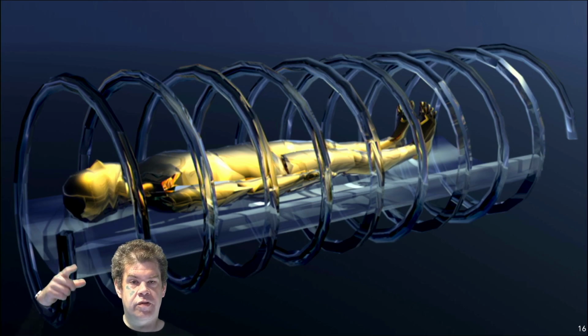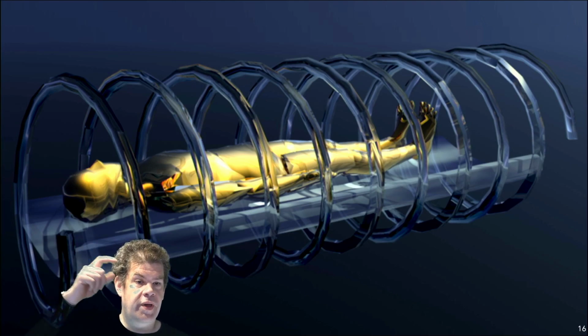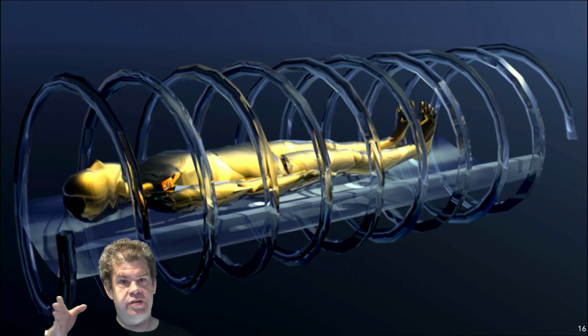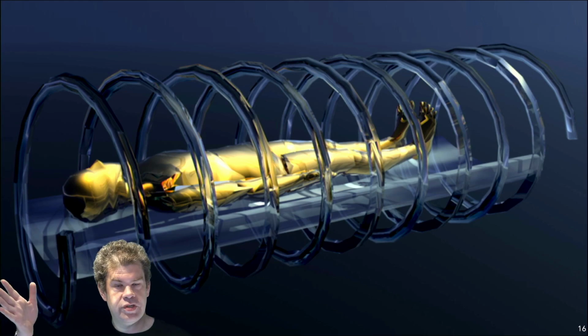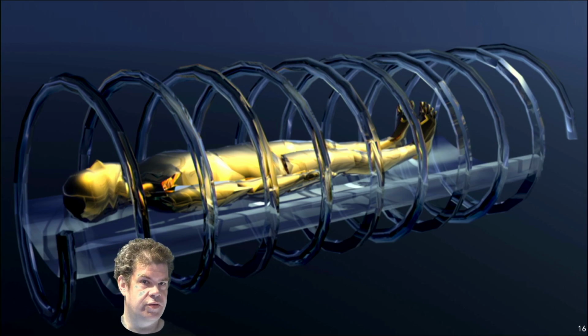If I looked at the position of the emitter relative to the patient, I would get this spiral path. This is why we call this setup spiral CT. Previously, you would do a revolution, then shift the patient, do another revolution, shift the patient, and so forth. That was the old type of CT, but that's not in use anymore. And I'll also explain why.